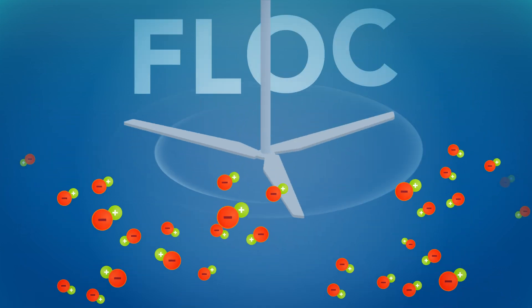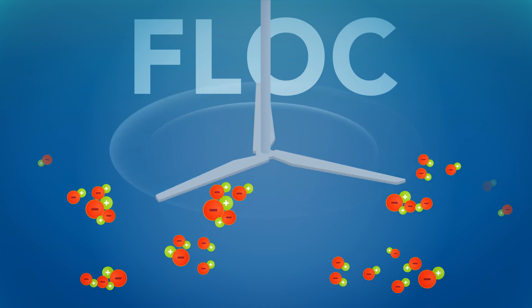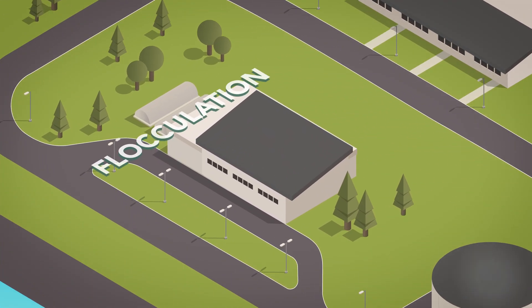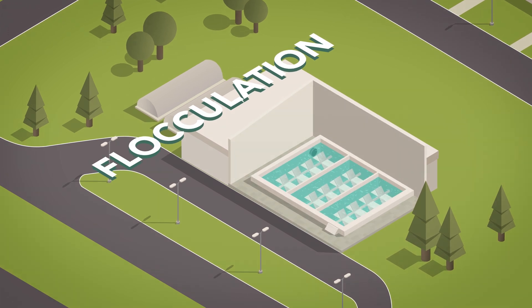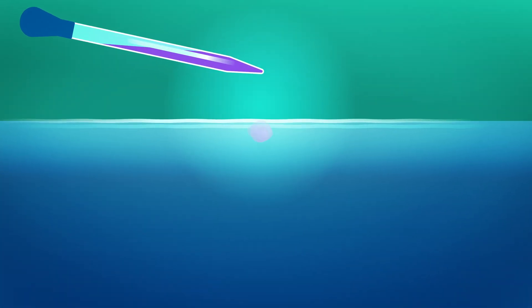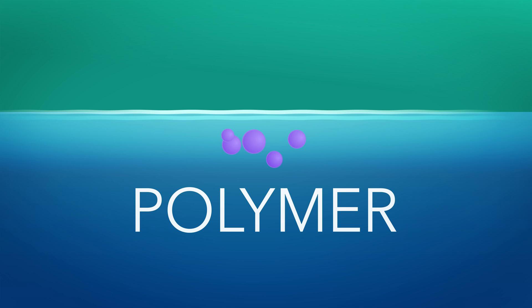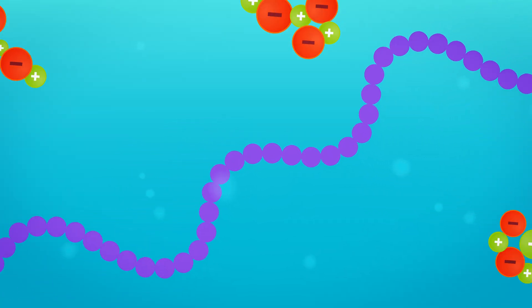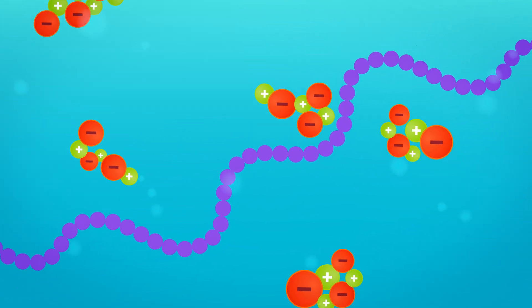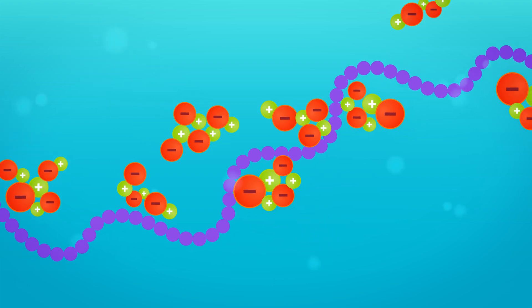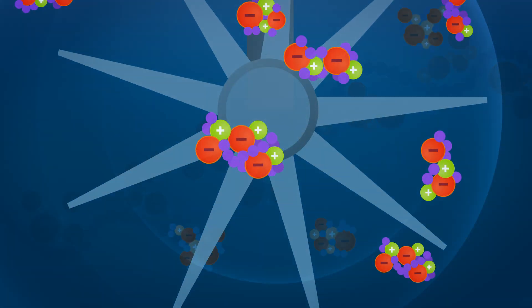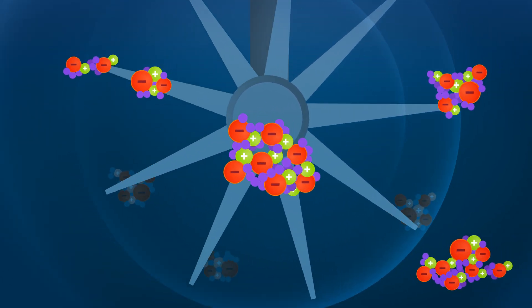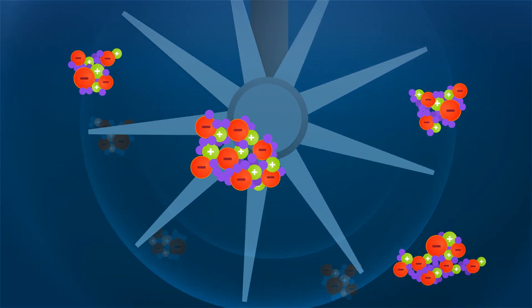These clumps of particles are called floc. The water then moves to the flocculation building. During the flocculation process, we add substances called polymers to the water. The polymers bind together with the floc to create larger chains of floc. The clumps flow through spinning paddles that help speed up the mixing process, and the floc clumps continue to get larger.